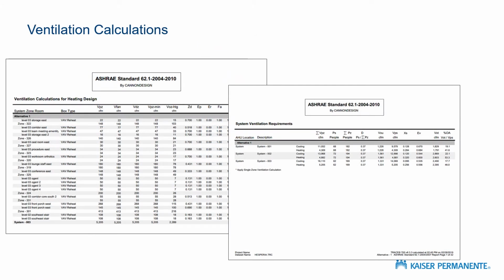So ventilation calculations. We've got to do ventilation calculations. In hospitals, ventilation is the number one and the primary energy driver. In medical office buildings, this slide has to do with medical office buildings. So for medical office buildings, this is pretty simple. We do want to see your standard 62 calculations. Those are the same calculations that you submit to USGBC. I know there's a couple different ways to do that. USGBC has a spreadsheet. I believe ASHRAE actually has a spreadsheet that they publish. And my understanding is that the latest versions of Trace can actually do those calculations right in your load calculations, which is pretty cool.